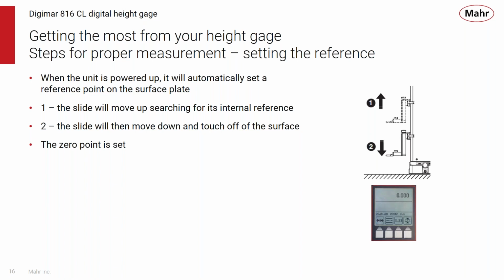Well, the first thing you want to do with any height gauge is set a reference point. So when the 816 is turned on, it's automatically going to set the reference point on the surface plate. As you power it on, you'll see the slide move up a little bit to find its internal reference. Then it's going to come down and touch off on the surface, and the 0 point is set. So you turn the unit on, it goes up, it comes down, touches the surface, and you get your 0 point set automatically for you.